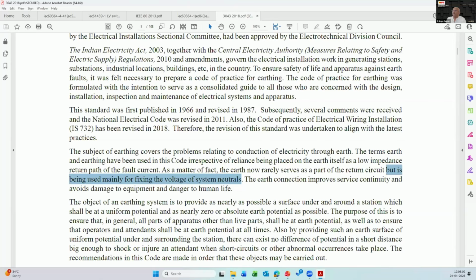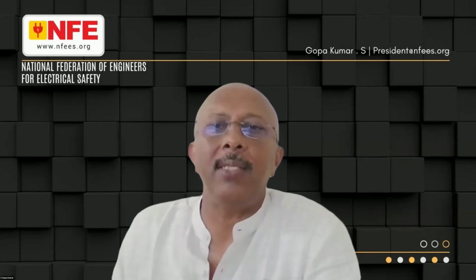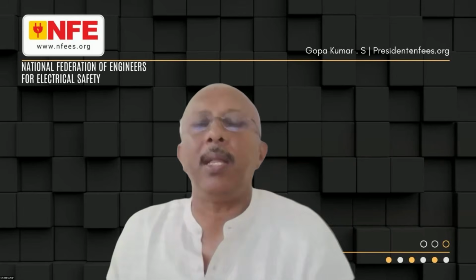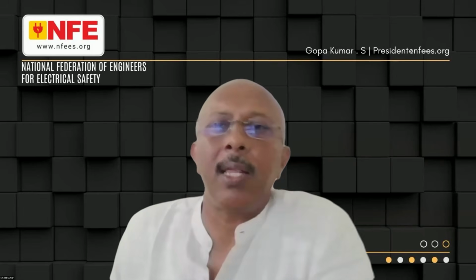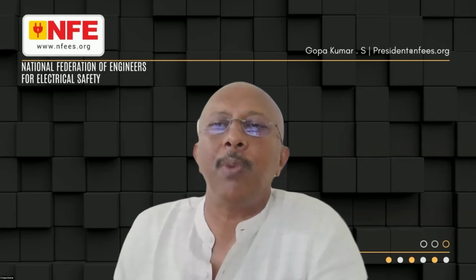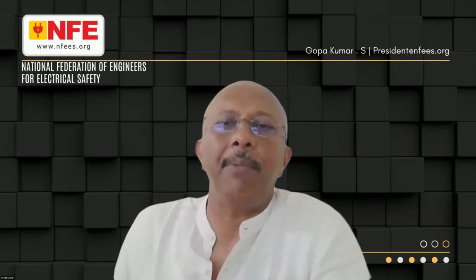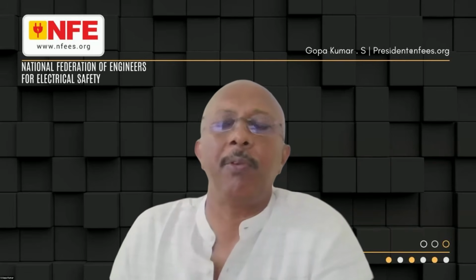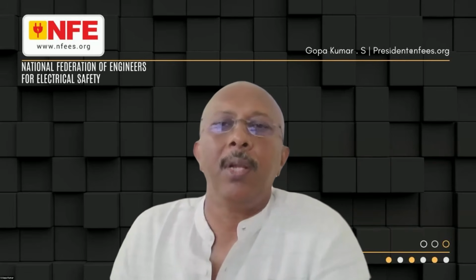That concept is wrong. IS 3043, as well as all the electrical standards, explain this particular subject. It's a misinterpretation that a lot of current will be flowing through the earth electrode. Probably 10 amperes, 15 amperes, or maximum maybe 100 amperes will be flowing for a short time, not continuously.